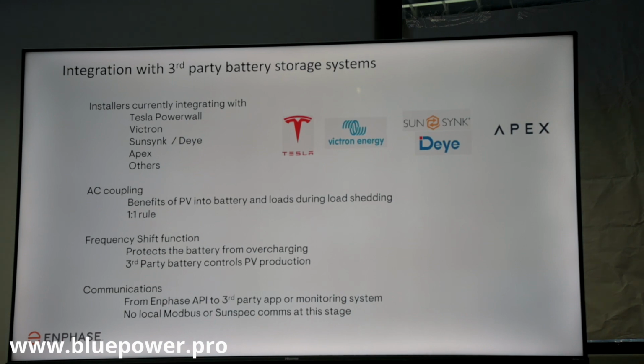So basically, AC coupling means that if you're plugging in on the output of a battery inverter, even if the grid goes down and the battery inverter makes an island, it will still produce energy on that island, on the AC network. It will go into the loads of that network, reduce the demand on the battery, and also charge the battery on the output side. One challenge: when the battery gets full, you need to stop charging it - you don't want to overcharge the battery. So you need to issue an instruction to the microinverters, and we do that through frequency shifting.